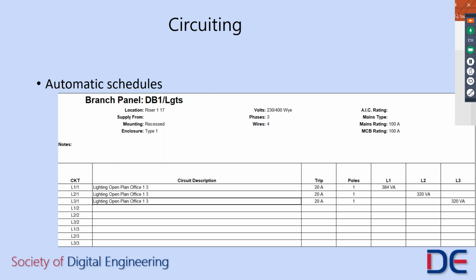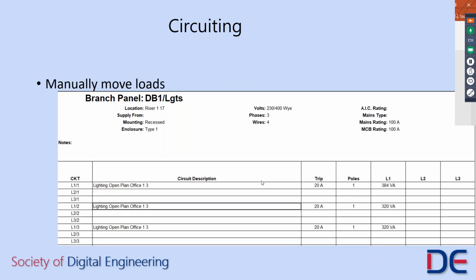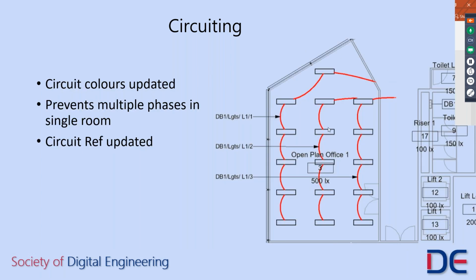This is another view of that circuit layout we just saw in the previous slide. And we can see here that the lighting load is spread across the three phases. So what we can now do is manually move those lighting loads so they're all on the same phase. We can then lock them to those circuit ways. And when we go back to our drawing, we can see that these are now all coloured red. And that's an automatic response to us moving them across the phase. We can also see that the circuits have changed from L1, L2 and L3 to all being L1 and different ways off the board. So all of that rejigging that we would normally associate with changing the text associated with circuits has all been automated for us. And also we now have the graphical assuredness that these are all on the same phase.